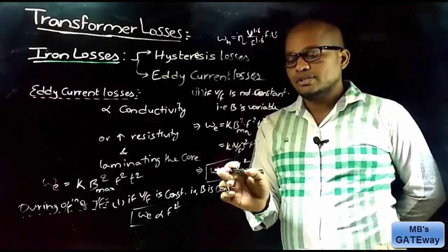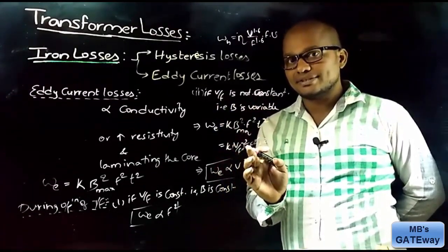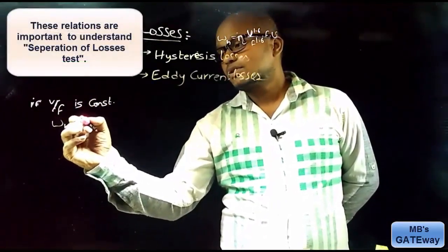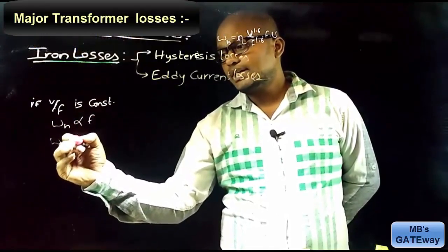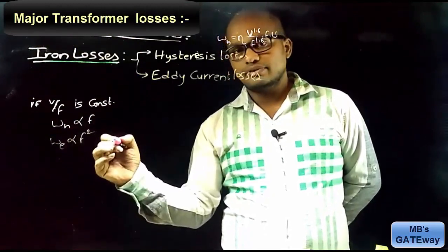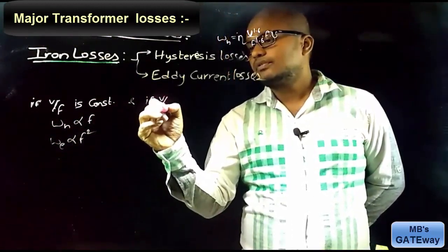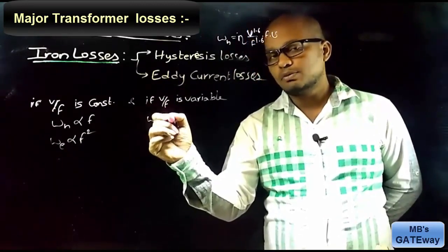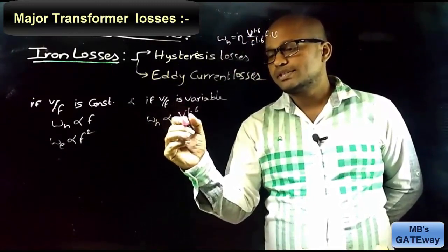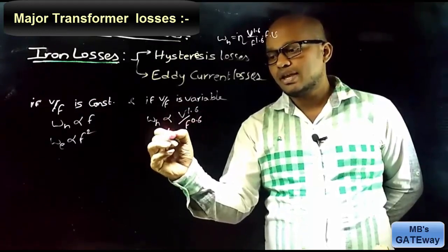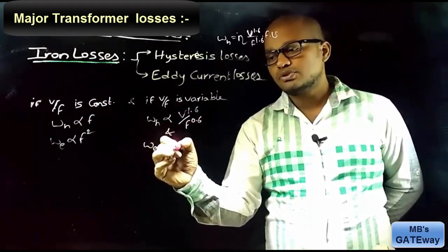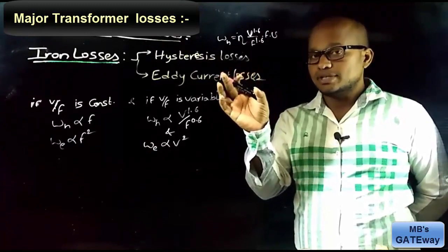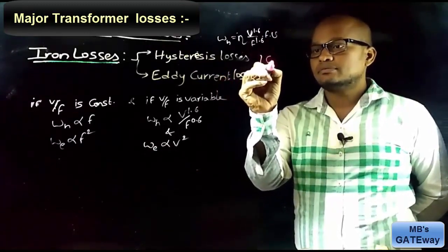To summarize: if the V/F ratio is constant, hysteresis losses are directly proportional to frequency F, and eddy current losses are directly proportional to F². If V/F is variable, hysteresis losses are proportional to V^1.6 / F^0.6, and eddy current losses are proportional to V² and are independent of frequency. Since input voltage is maintained constant, both these iron losses come under constant losses.